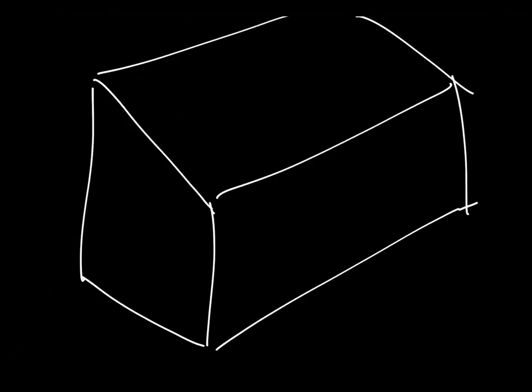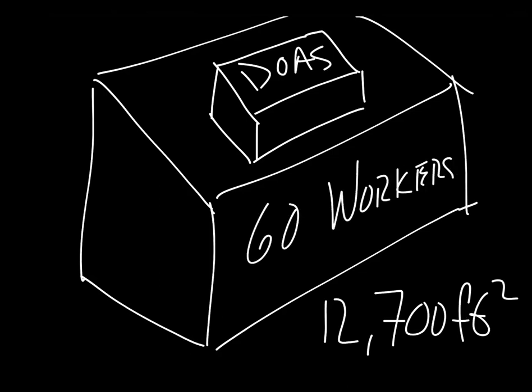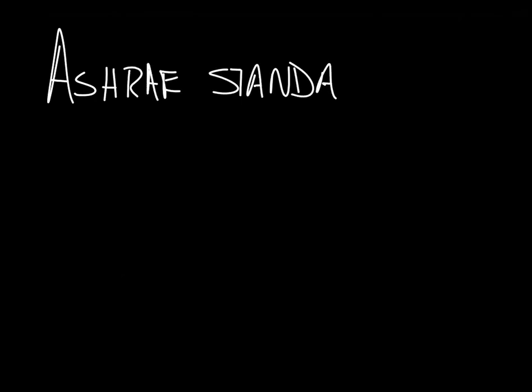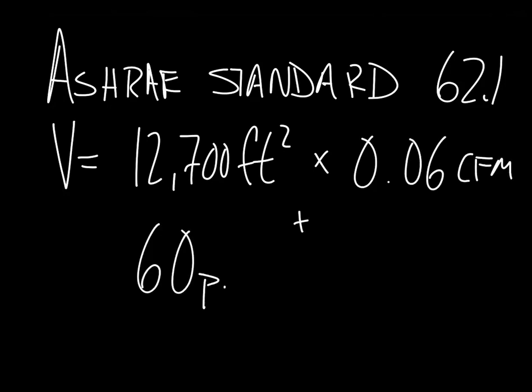If we take a hypothetical office building of 12,700 square feet, being fed by a dedicated outdoor air system with 60 workers, the minimum ventilation rate per ASHRAE standard 62.1 is calculated by the square footage times 0.06 CFM per square foot.